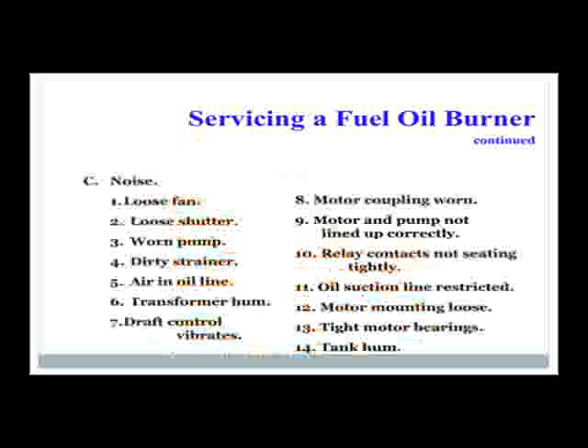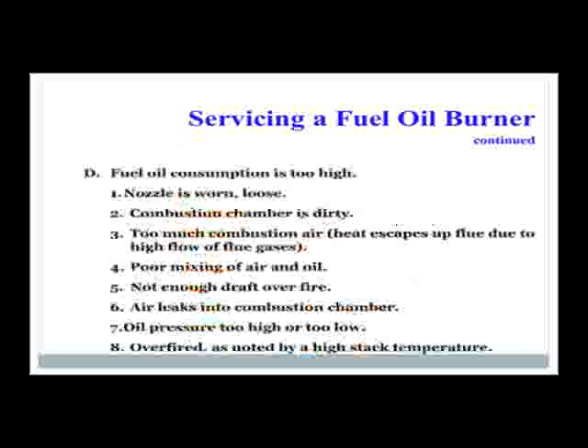Noisy furnaces: loose fan, shutters, worn pumps, dirty strainers, air in the line, might have some transformer humming, couplings. Look for anything that might make noise. Fuel oil consumption too high, look for bad nozzles, look for dirt, look for poor mixing of oil, check drafts, check for air leaks, check oil pressures, and check to make sure it's not overfired, and you can tell this by high stack temperature.